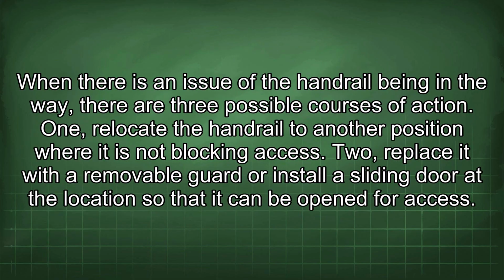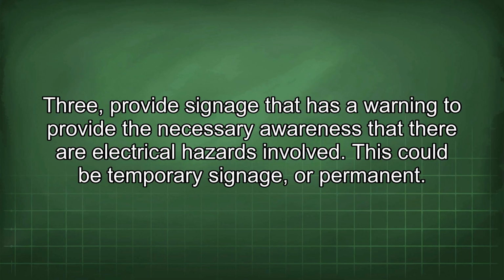When there is an issue of the handrail being in the way, there are 3 possible courses of action. 1. Relocate the handrail to another position where it is not blocking access. 2. Replace it with a removable guard or install a sliding door at the location so that it can be opened for access. 3. Provide signage that has a warning to provide the necessary awareness that there are electrical hazards involved. This could be temporary signage or permanent.